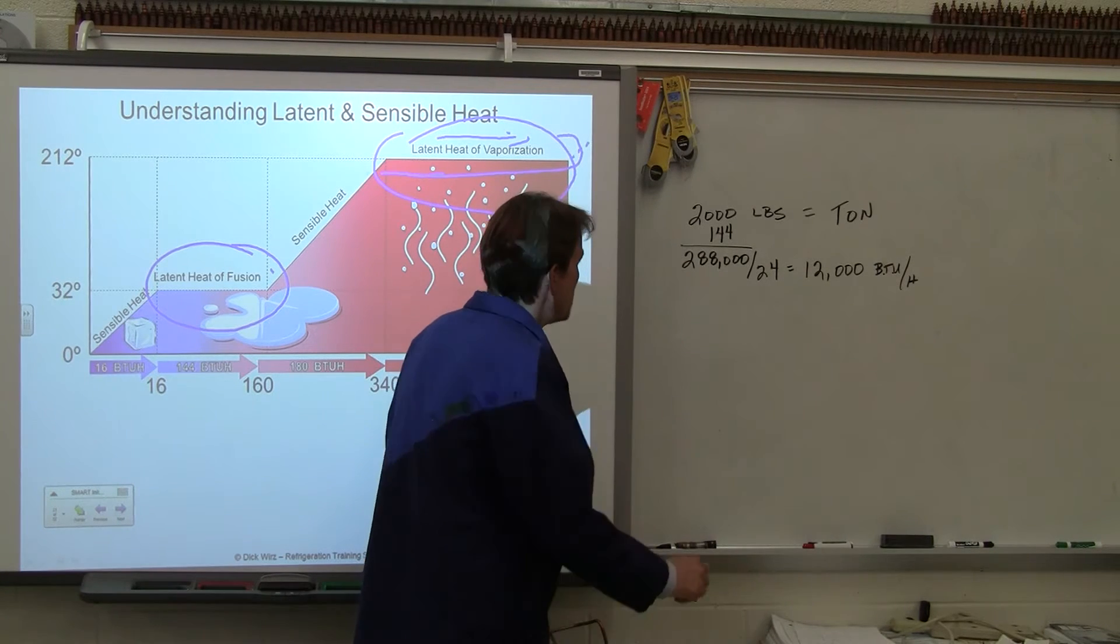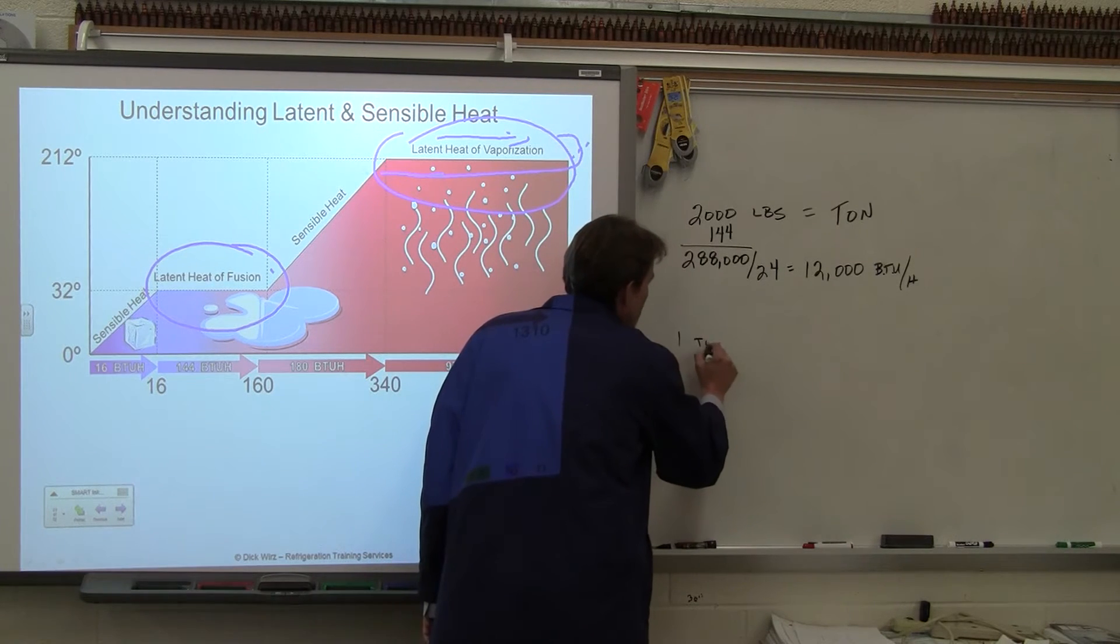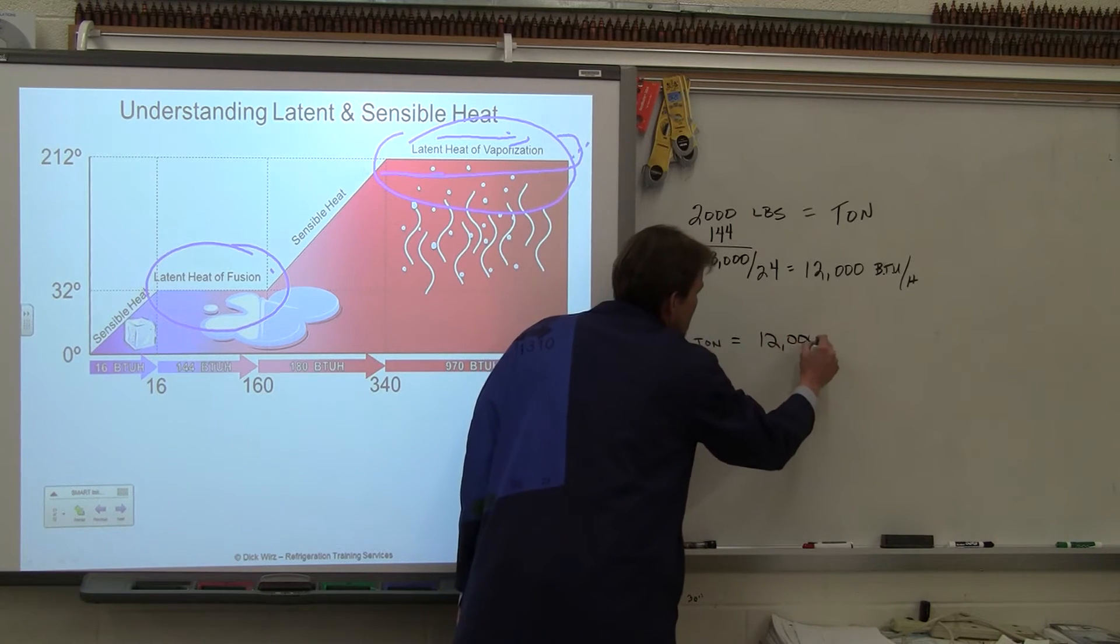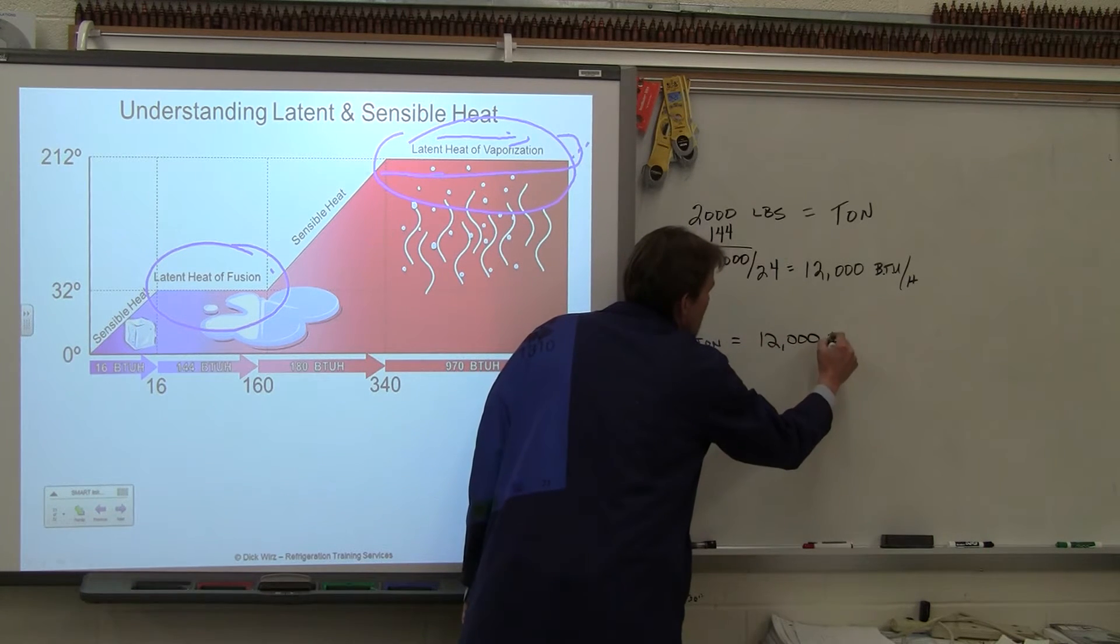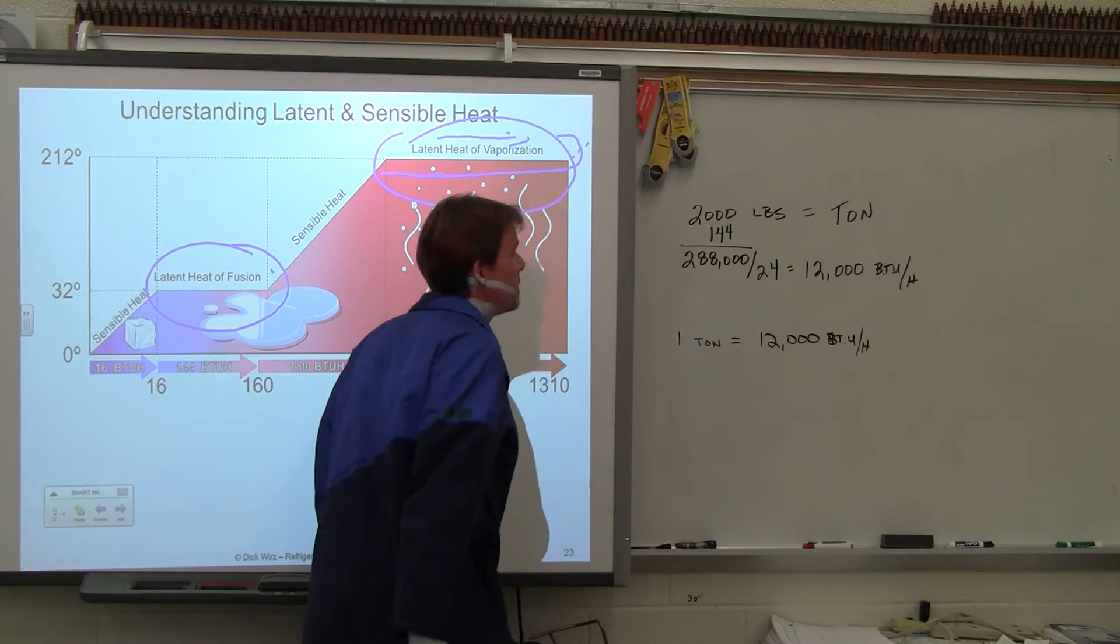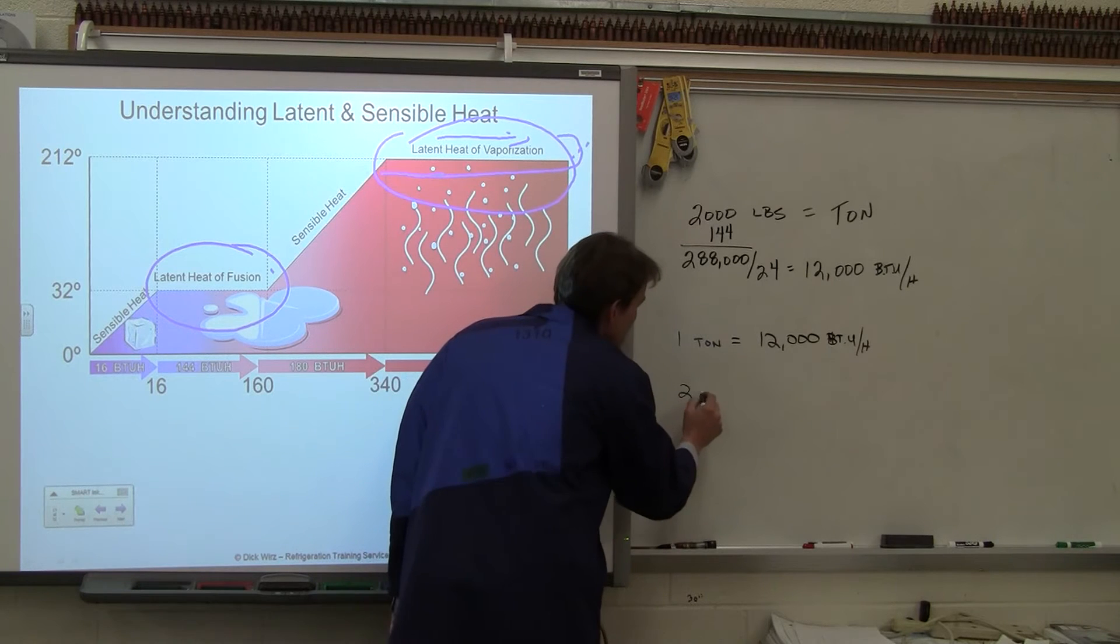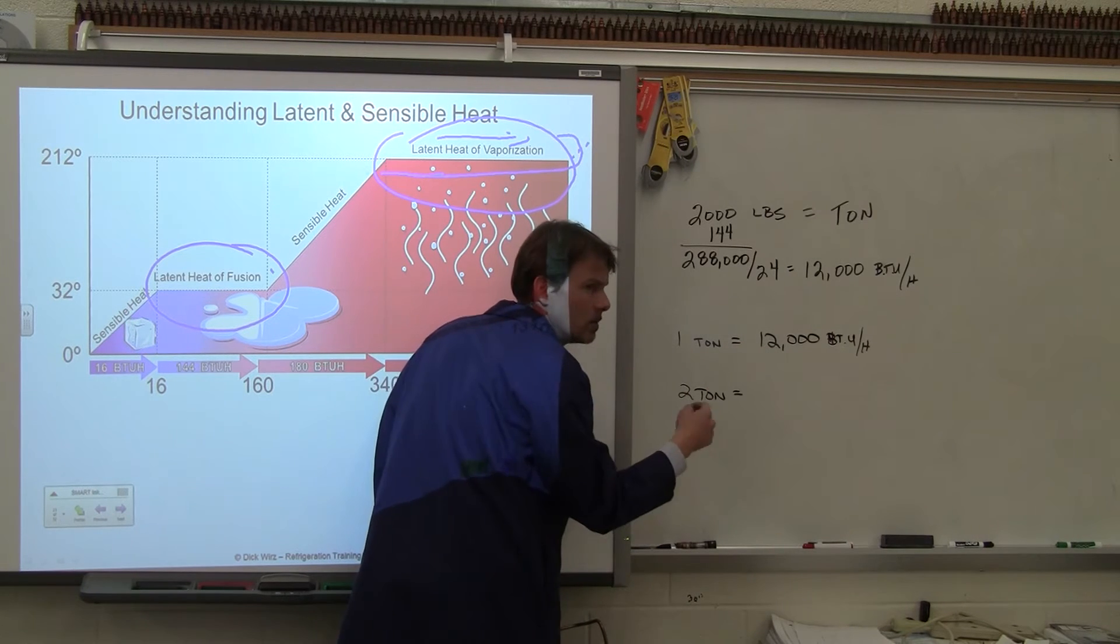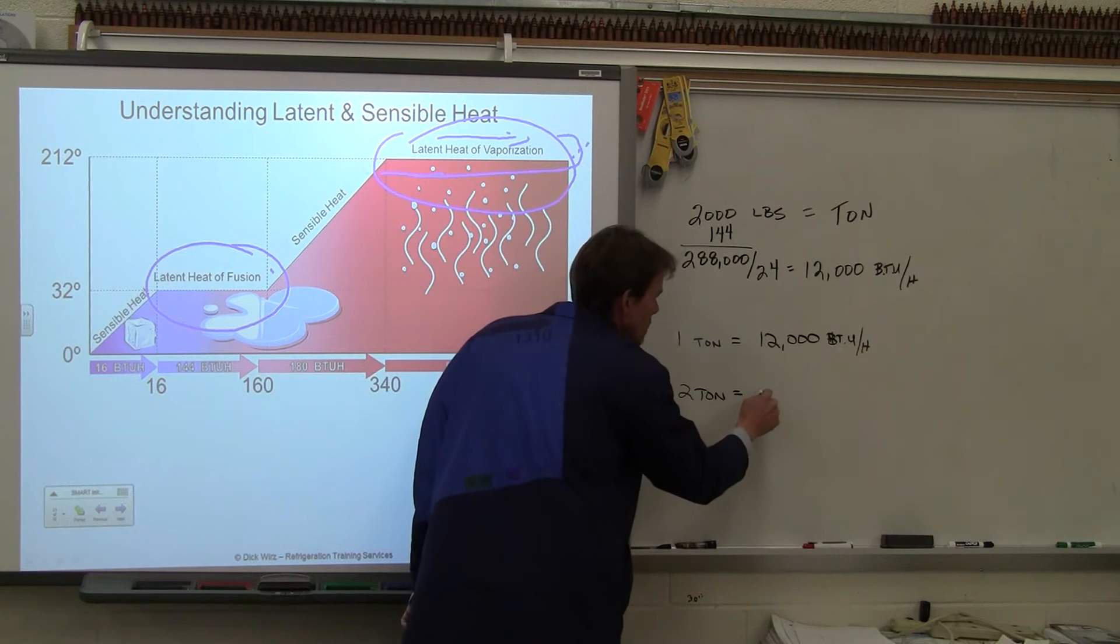That's where they get the 12,000 BTUs from. So if you hear somebody say they have a 1 ton unit, what that means is that unit can remove 12,000 BTUs worth of heat in a one hour period. And then if it's a 2 ton unit, then how many is that going to be? So 1 times 12,000, how many is 2 gonna be? 24,000 BTUs.